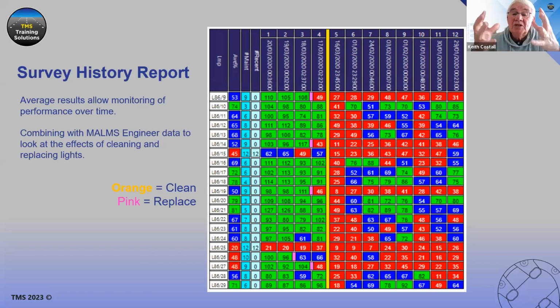The actual figures - this spreadsheet shows exactly. What's interesting is you'll see a big orange line, though it looks yellow on my screen, and prior to the right-hand side of the spreadsheet you'll see lots of reds, with column 5 entirely red. That means the lights with that ID on the left-hand side were all unserviceable, below 50%. Therefore, we cleaned all the light fixtures, and in cleaning them, look at the improvement in column 4.